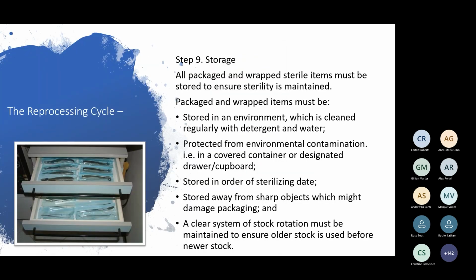For step 9, storage. All packed and wrapped sterile items must be stored to ensure sterility is maintained. They must be stored in an environment which is cleaned regularly with detergent and water. So this is what I was talking about. This needs to be recorded on your cleaning guidelines as well. They need to be protected from environmental contamination. So they must be in a covered container or designated drawer and cupboard that can be closed, stored in order of sterilizing date. So make sure that you're putting your longest from sterilization date at the front and the newest sterilization date at the back, stored away from sharp objects which might damage the packs, and a clear system of stock rotation must be maintained to ensure older stock is used before newer stock.